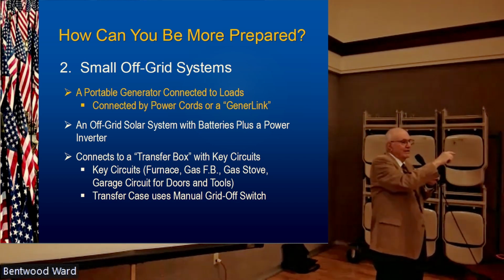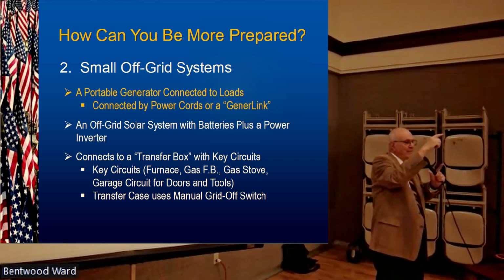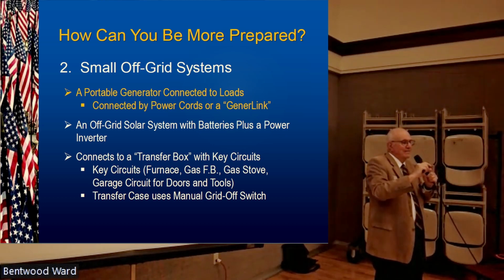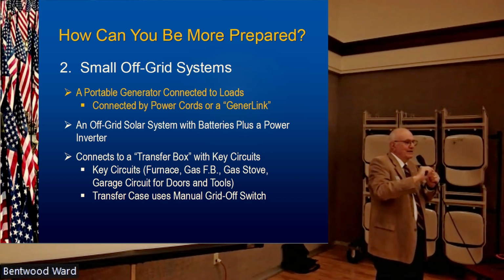You divert 6 to 8 circuits off your big panel into this box. It gives you the ability to switch it to the generator plug or to the grid, so it's safe for the lineman. You're never going to backfeed.